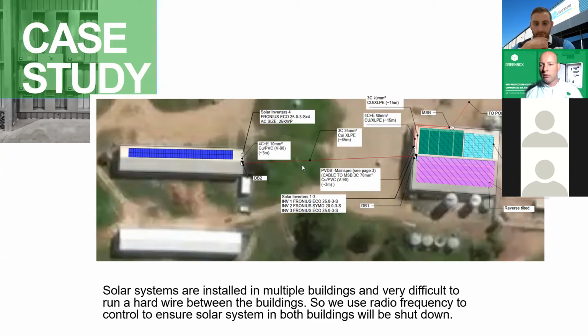One other thing we briefly spoke about is the injection test. Not every DNSP requires it, but again, some do. And if they do, this is also an area where we can help you out to do that complete test. It's not a simple test, it takes the guys about 4 hours to run through and actually prove that the grid protection device shuts down as per the statement of the DNSP. Then you get an official report, which you have to hand in to your DNSP.